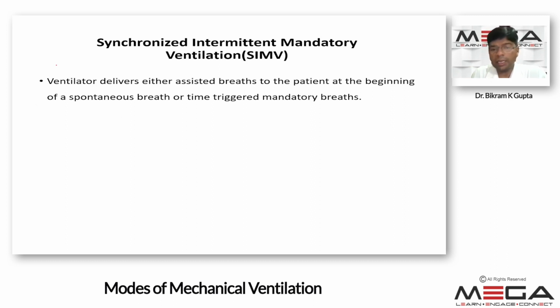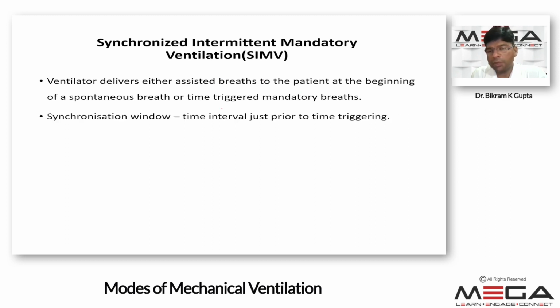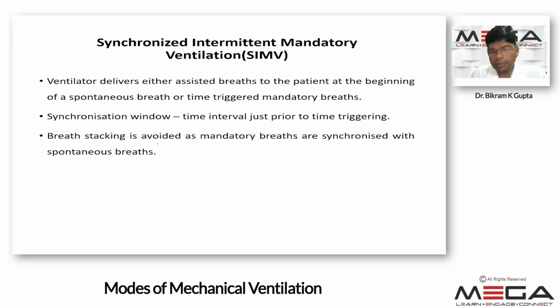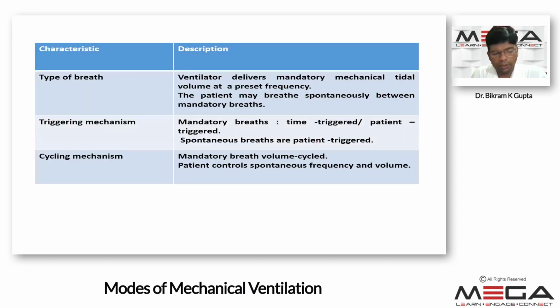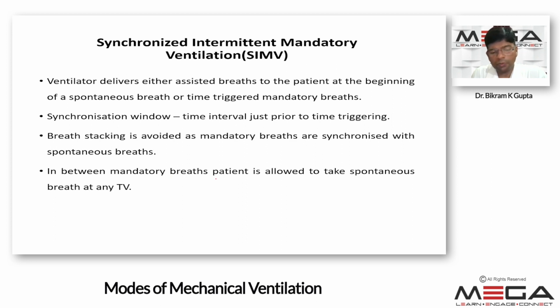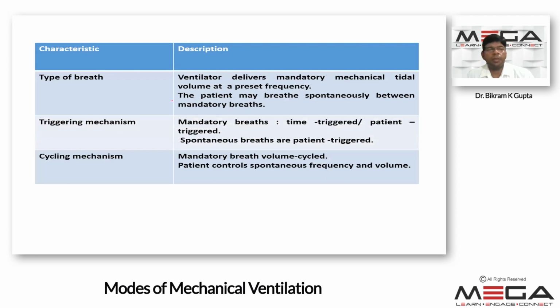In this, the ventilator delivers either an assisted breath to the patient at the beginning of a spontaneous breath, or time-triggered mandatory ventilation breaths. There is a synchronization window to prevent breath stacking, which is a major problem in intermittent mandatory ventilation, and the synchronization window is the time interval just prior to the time trigger. Because of that, breath stacking is avoided, as mandatory breaths are synchronized with the spontaneous breath. In between the mandatory breaths, the patient is allowed to take spontaneous breaths at any tidal volume. So the characteristics of SIMV: the ventilator delivers the mandatory mechanical breaths and the patient can take spontaneous breaths in between. Mandatory breaths are time triggered or patient triggered, and spontaneous breaths are patient triggered. For the cycling mechanism, mandatory breaths are volume cycled and spontaneous breaths are flow cycled.